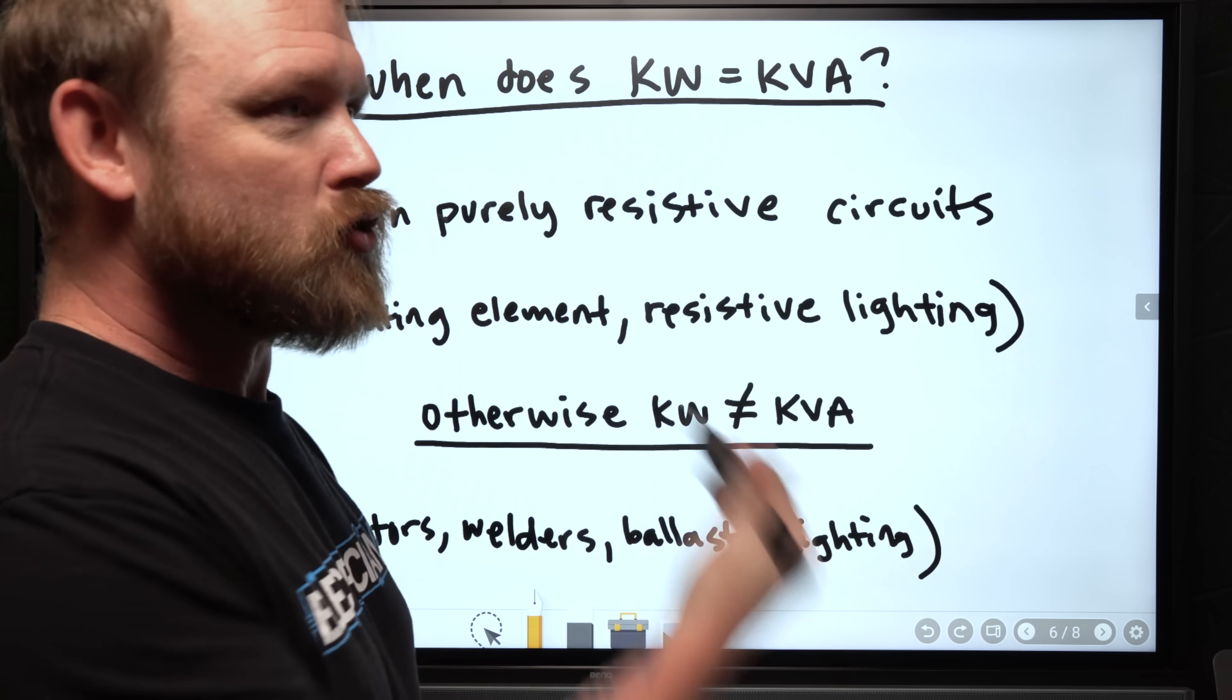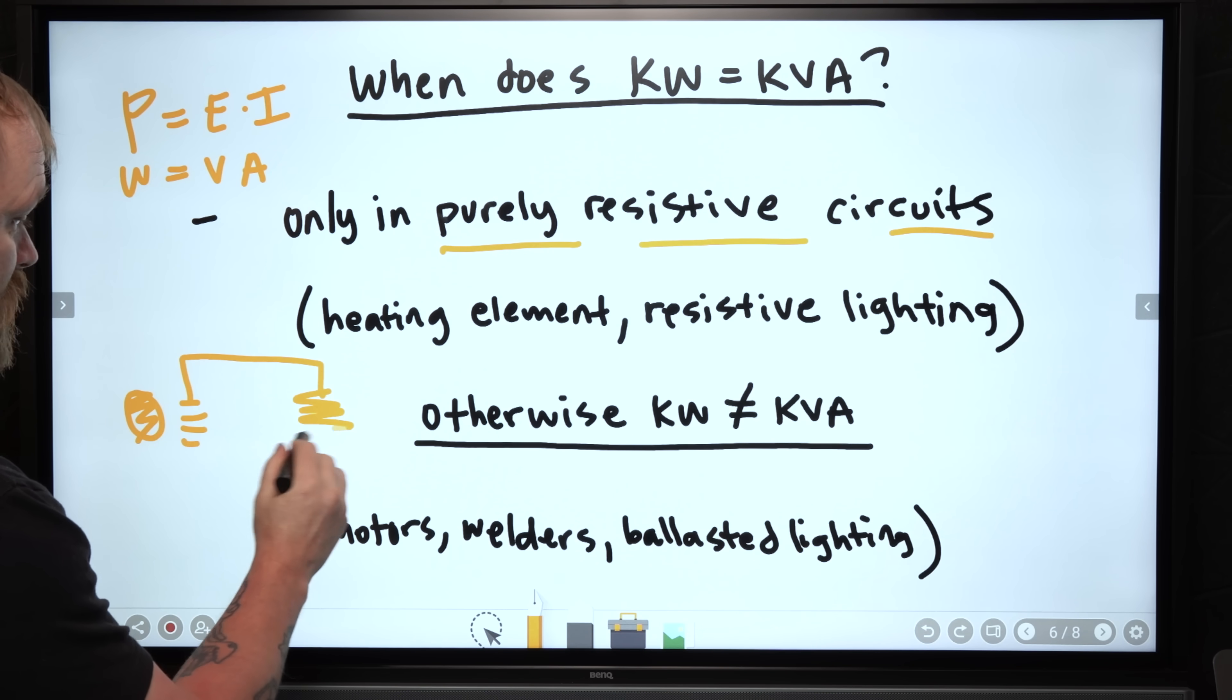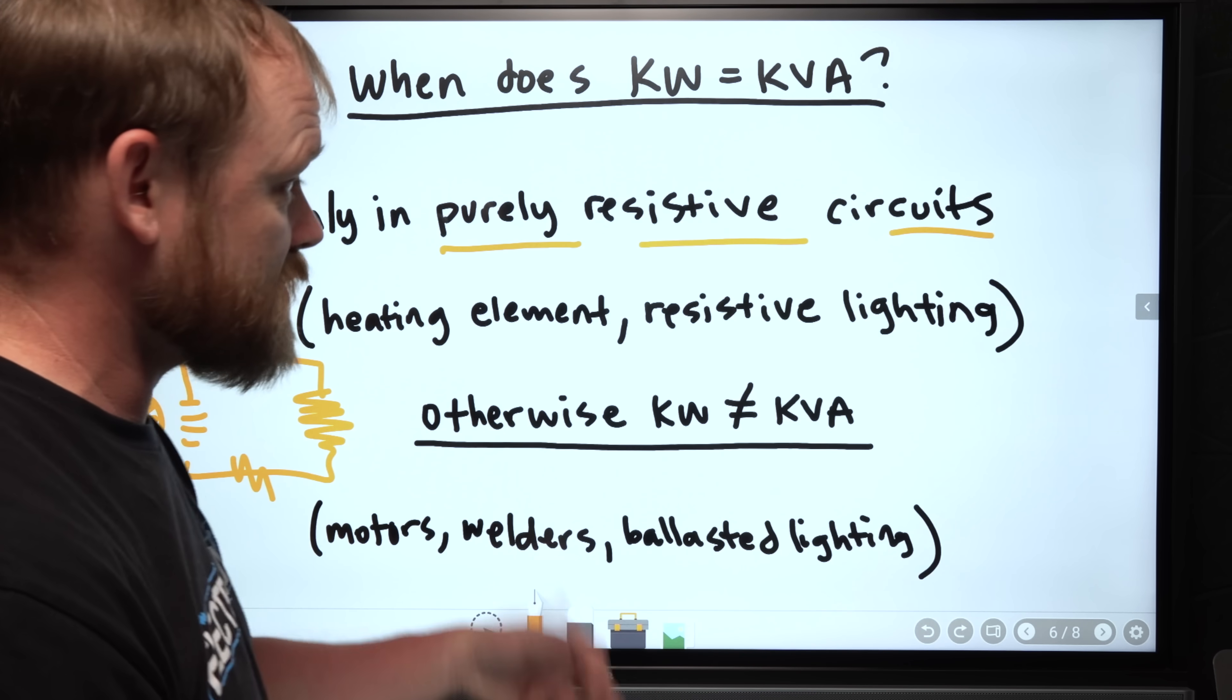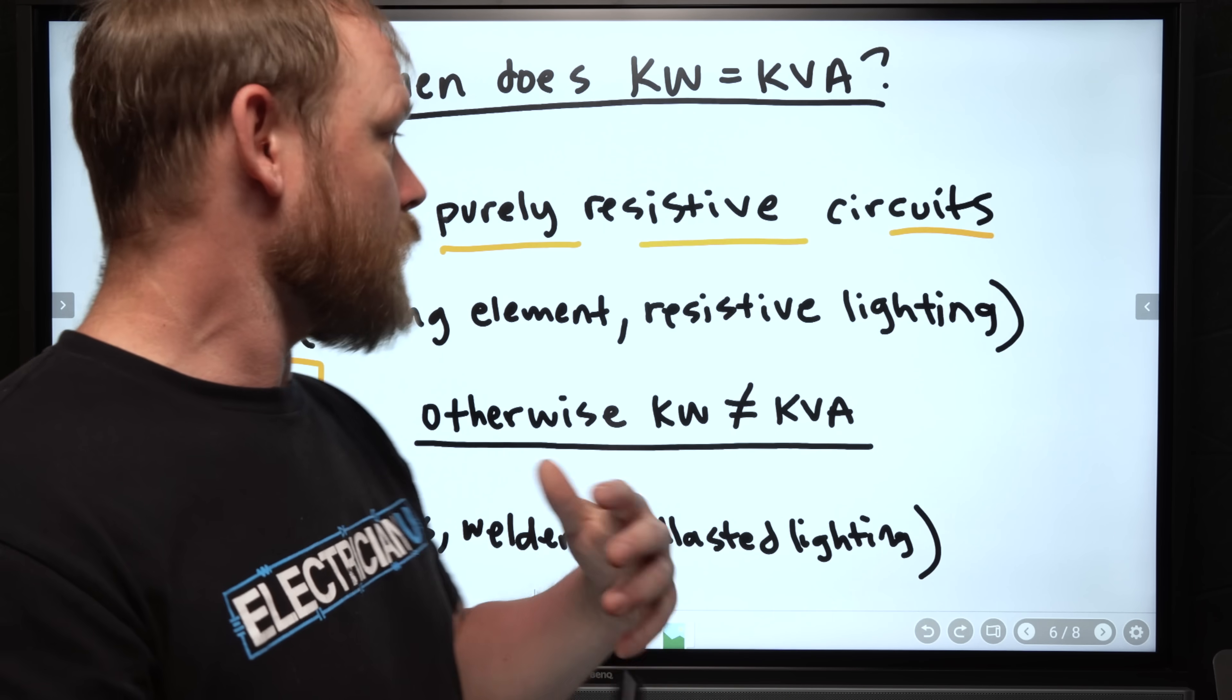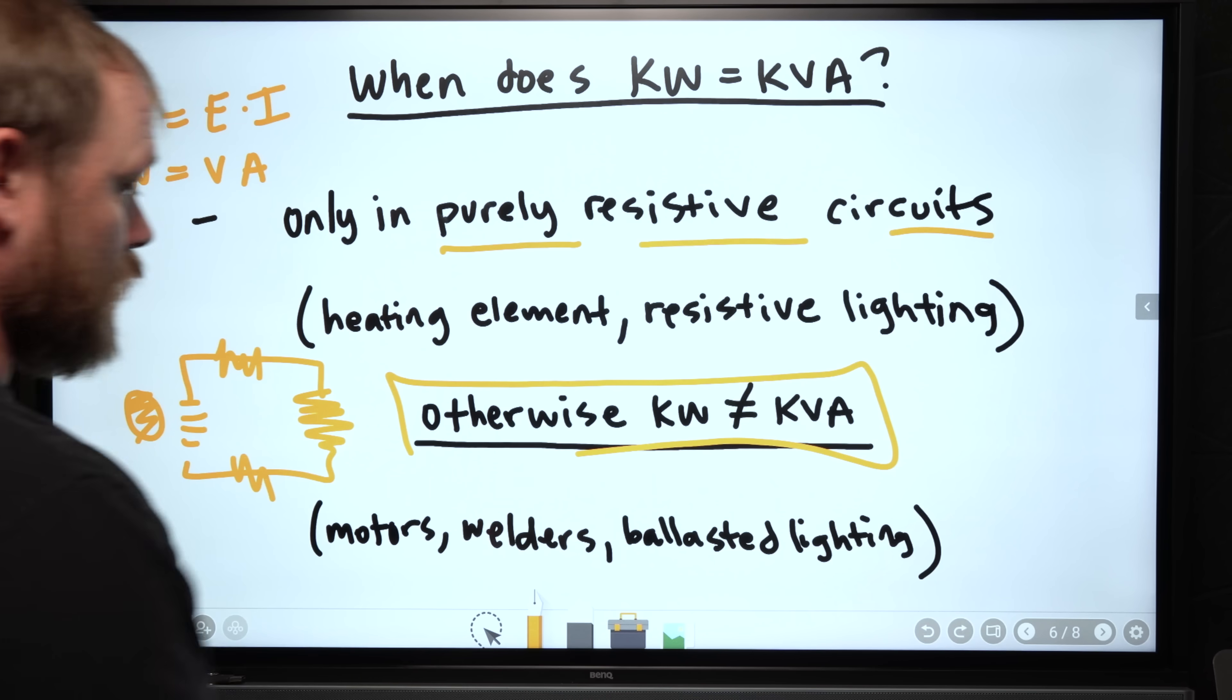So when does KW equal KVA? Really, if you're doing a power formula calculation, watts equals VA, a watt equals a volt amp. That's kind of the only time you're ever going to see it. It's just theoretically true. But it's only true in purely resistive circuits. And that is a circuit with a resistor or only several resistors, no inductors, no capacitors. It's purely resistive, only resistance. If you have a heating element, a heating element is going to be a large resistor. If you have resistive lighting, like incandescent lighting is essentially just a resistor. So it's possible that whatever is supplied to this thing, you're going to get an equal consumption out of it.